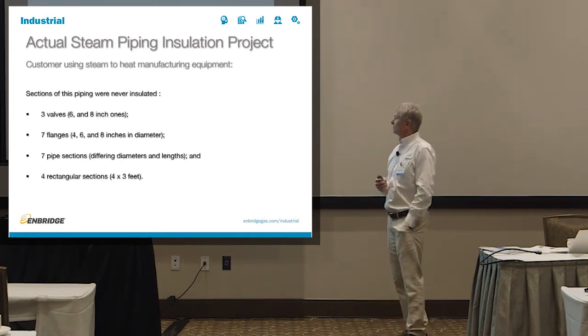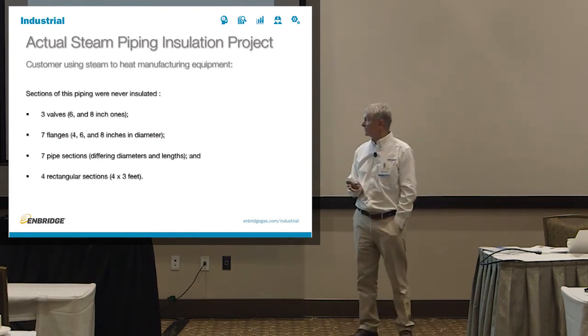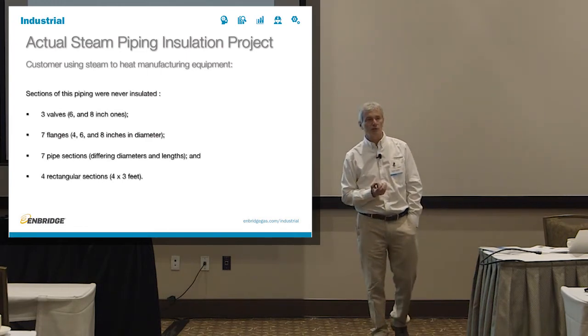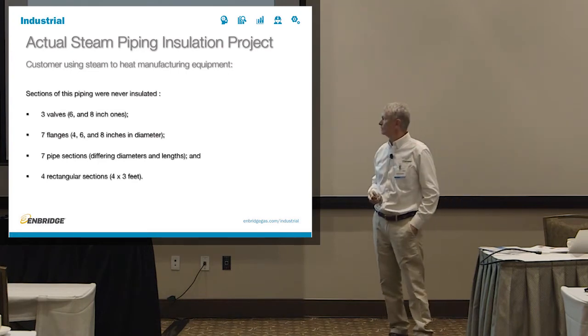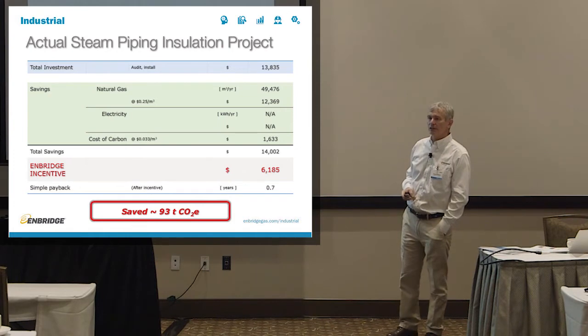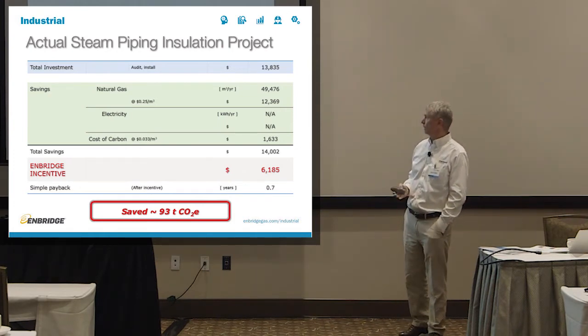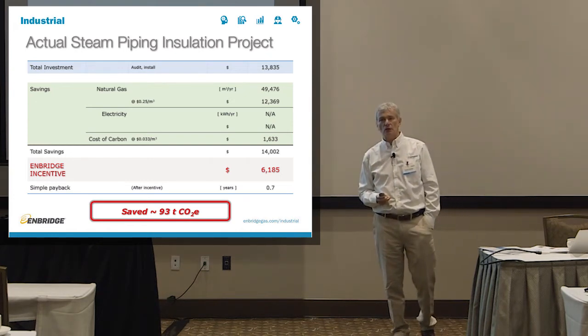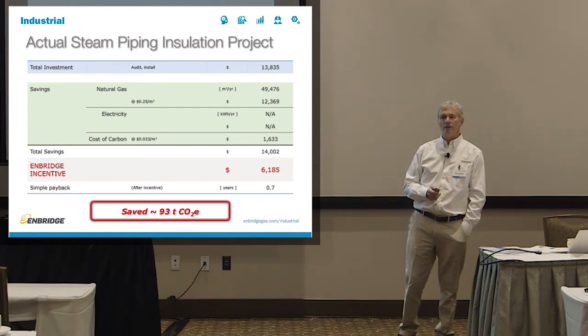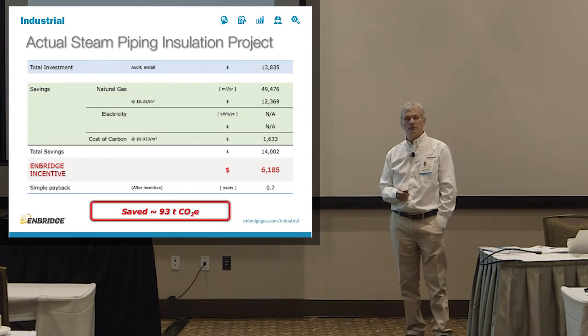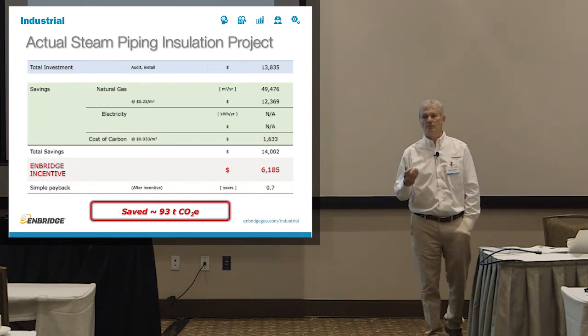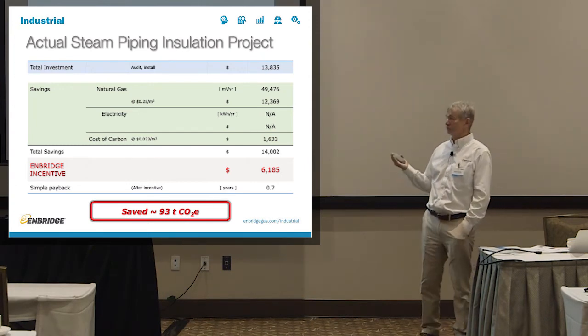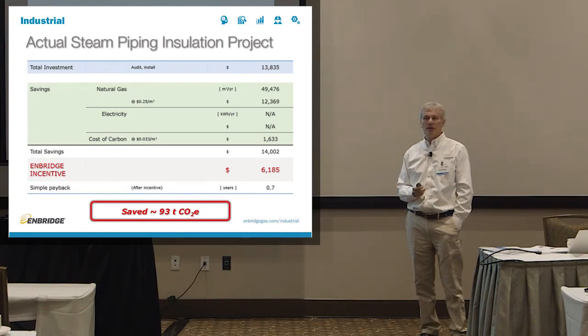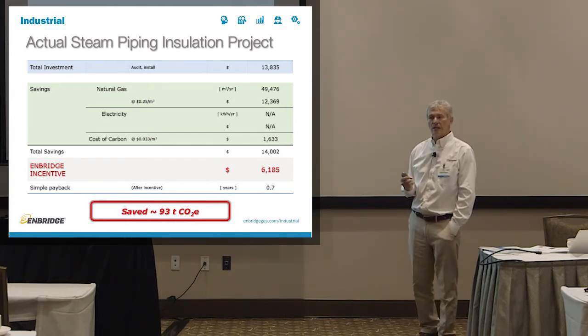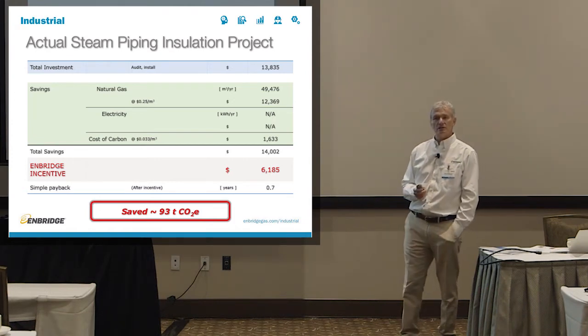Example. A project that we've done with a customer, steam piping. We insulated 3 valves, 7 flanges, 7 pipe sections, and 4 rectangular sections. So a small part of the system, not all of it. These are the results. $14,000 investment generated $14,000 savings, 1 year payback, and with our incentive of $6,000, that practically brought it down to about a 6-7 month payback. That saved them about 93 tons of CO2e, 100 tons of CO2e saved just by insulating the pipes that are sitting there. For a total investment of $13,000 minus $6,000 in rebates, $8,000. So not a big investment, fairly significant savings. 50,000 cubic meters saved.